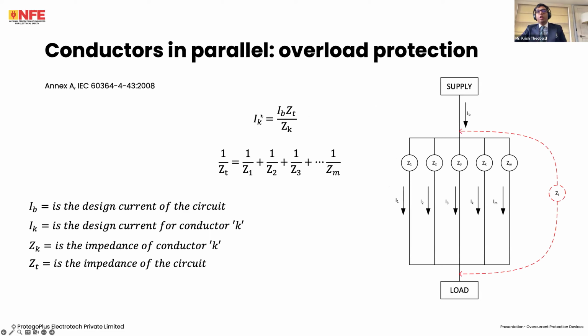How do we calculate it? Well, for the current Ik, you can calculate it as the total design current multiplied by the total impedance of all the conductors in parallel, divided by the impedance of this actual run itself. Obviously, we all learned this in high school. We know how to do this. Simple parallel impedances. Obviously, because the impedance of all these conductors in parallel is going to be much less than the impedance of this run in particular.